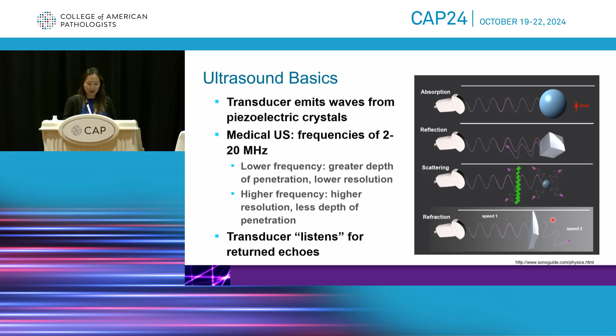And usually for medical ultrasound, you end up in the frequencies of 2 to 20 megahertz. And the important thing to know about this is that lower frequencies are going to give you greater depth of penetration, but lower resolution. Whereas for higher frequencies, you're going to get higher resolution, but the waves aren't going to penetrate as much. So depending on what your application is, you might want to use different frequencies. And often your ultrasound machines, if you have them, will come in with presets, and ours does.